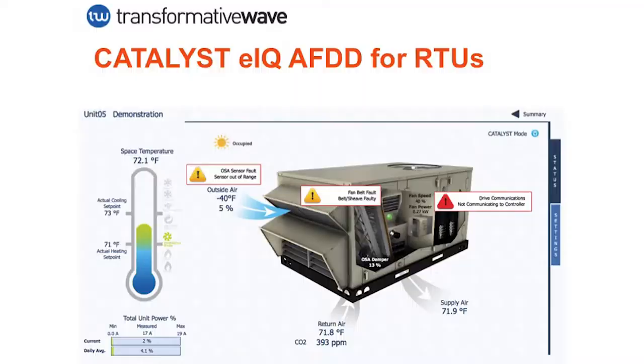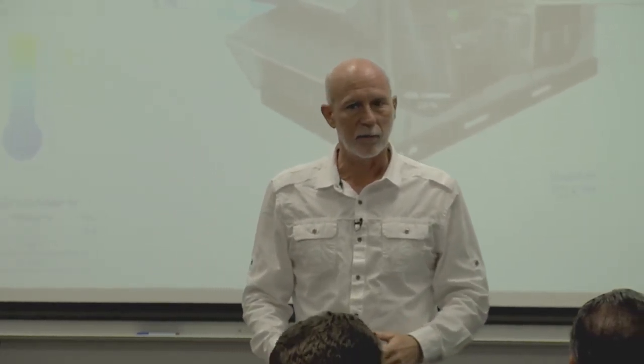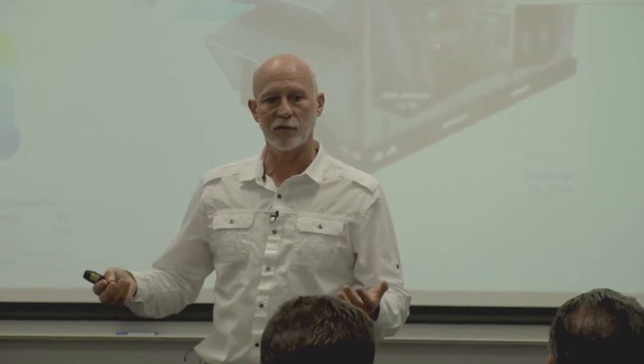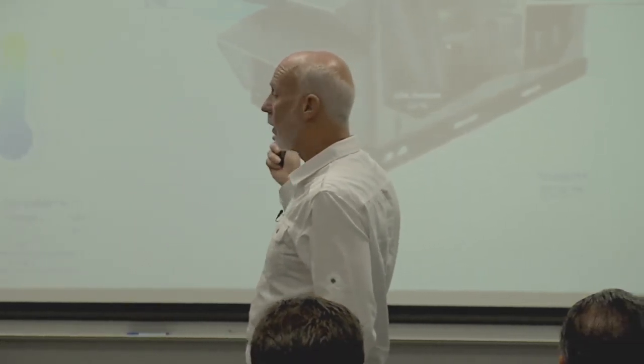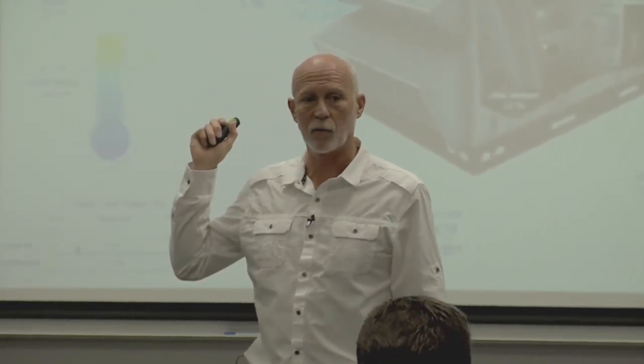With this fan belt fault, there's an energy signature we pick up through the catalyst drive, the VFD on the supply fan, that tells us when fan belts are slipping or something is out of alignment in the fan section. About three weeks ago we had one of the greatest testimonies to the value of that fault. We don't know anybody else who does this.